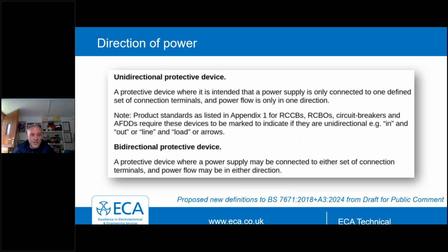Unidirectional, okay, our energy or our power is only going to flow one way. So most of our circuits are unidirectional. Bidirectional is where energy or power goes both ways, and we need to take into account how we wire up those protective devices, because if energy flows both ways, we need it to function, we need it to open, we need to make sure it's going to be great when things are bad. Okay, we don't want the device to fail and we don't want reduced capacity. And this is the big thing about checking with the manufacturer the suitability of those devices.